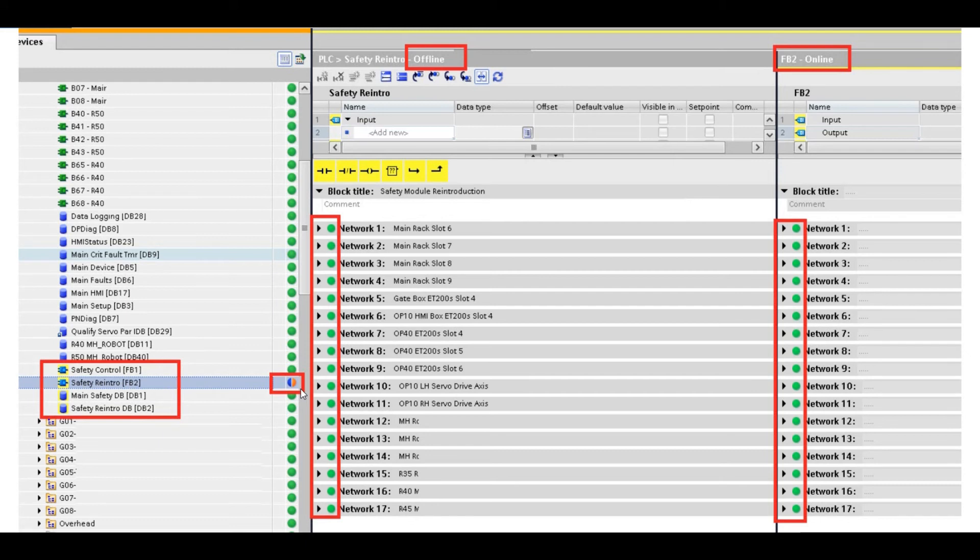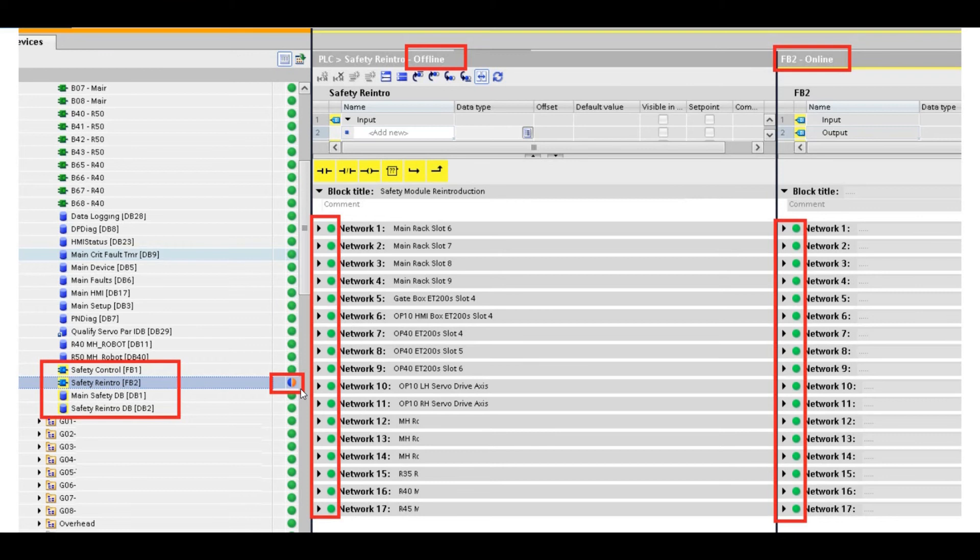And third thing, you know, to download the safety, the whole controller needs to restart. In your project, you have a lot of DB there. If the system gets a restart, maybe some existing data will be lost. If some data was not set as retain, once you restart the system, that data will be lost. That will be a lot of potential issues there.